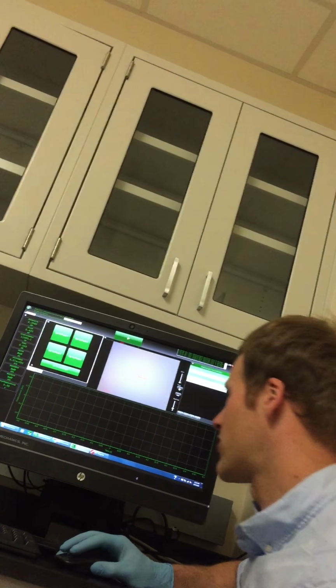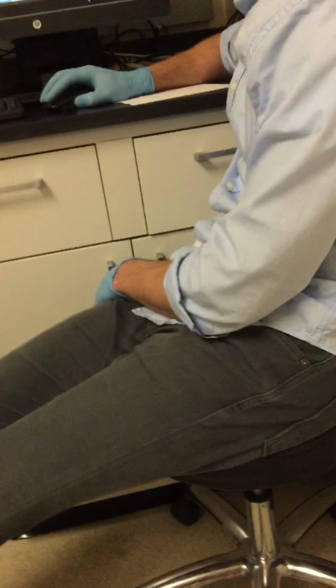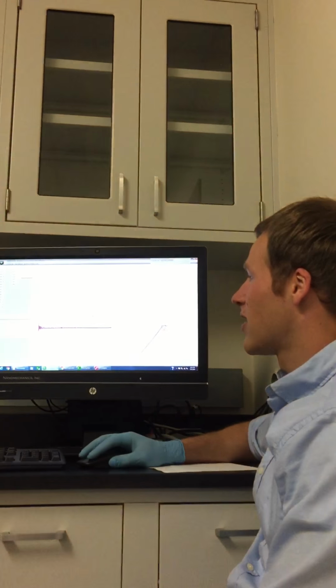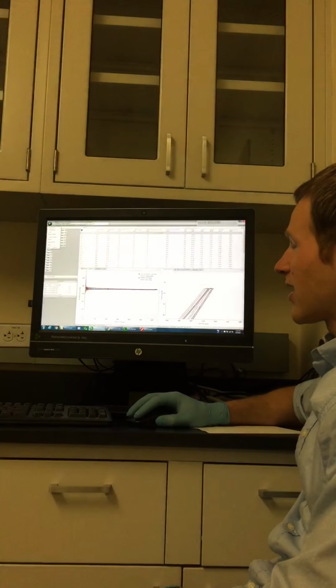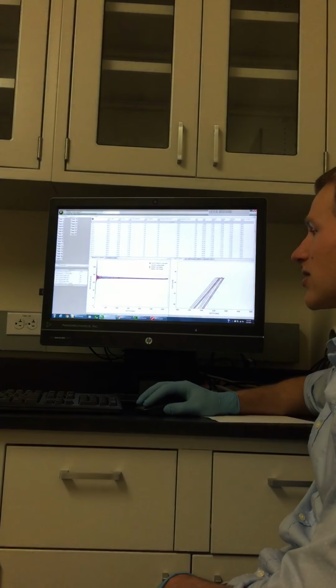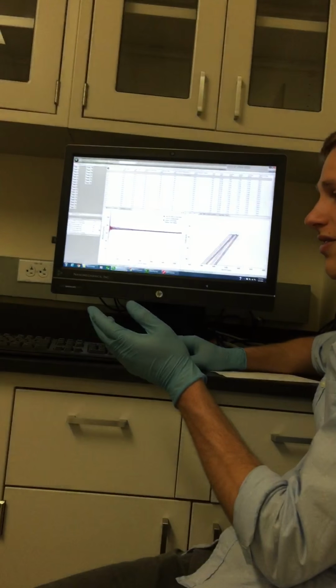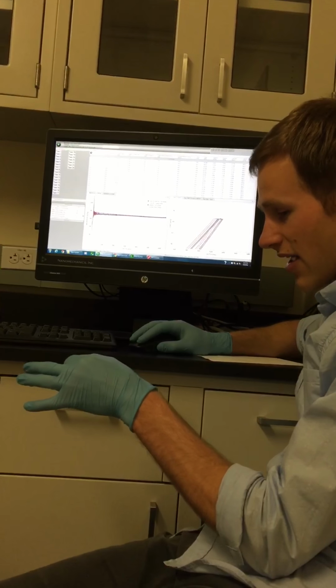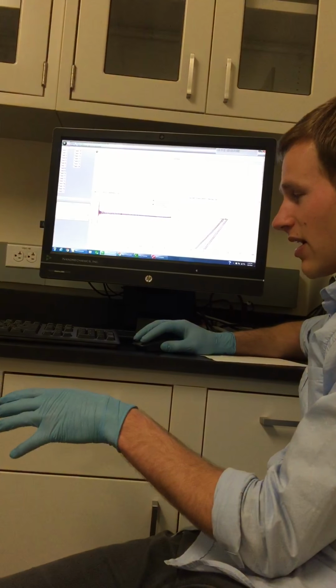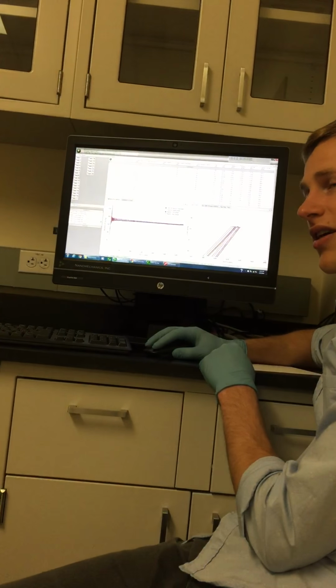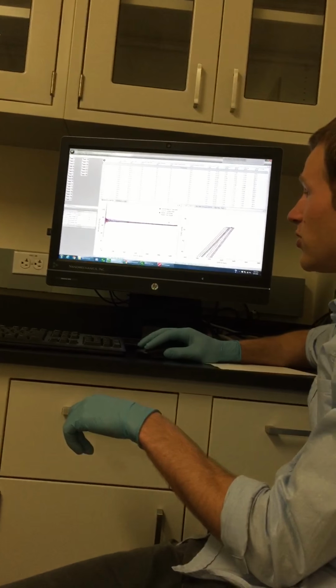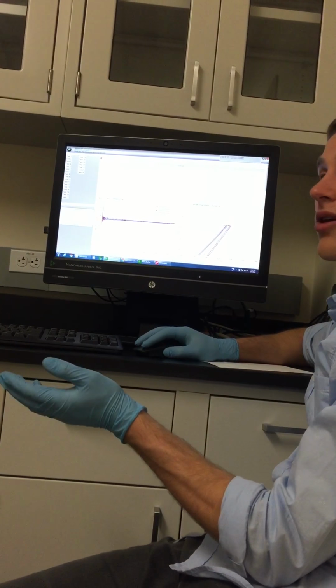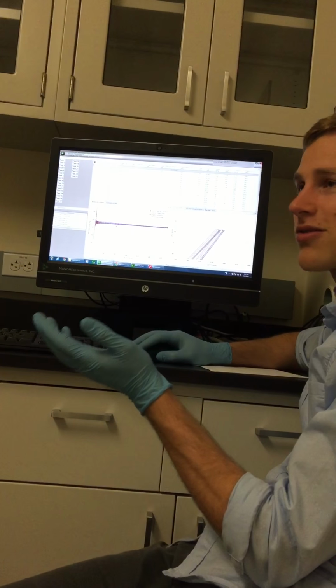So that's the calibration procedure, and again, it's outlined probably better than what I can show you right here. And another trick is that by changing the tip here, I can actually change the calibration I apply to a certain data. So I can take this data with an old calibration, I can recalibrate the tip on the fused silica, and then I can apply that new calibration to this data and see what it does. It's not always useful, but just so you know, you can do that.